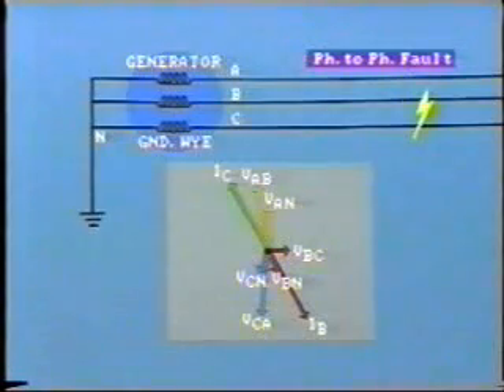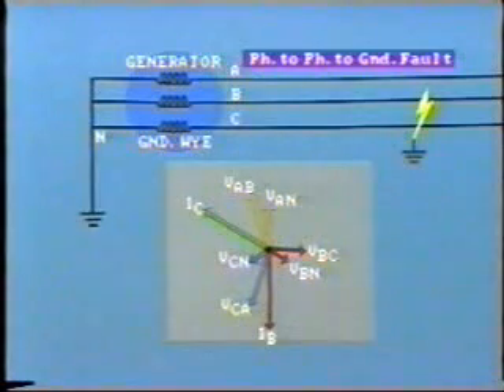In the phase-to-phase fault, the magnitude of the voltage between the two shorted phases at the fault will fall close to zero, and a heavy fault current will circulate in those two lines. In the phase to phase to ground fault, the voltage will fall in the two faulted lines.